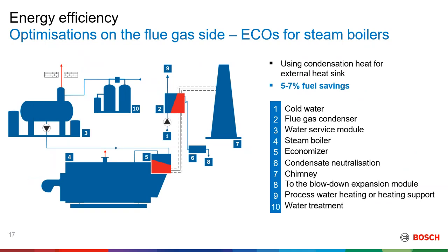For the condensing economizer, the water doesn't have to flow into the boiler. The heated water can be used for process downstream. In this setup, you can see water flowing from, let's say, a water treatment plant into the condensing economizer, number 2, and then into water heating or heating processes in the plant. Next slide.